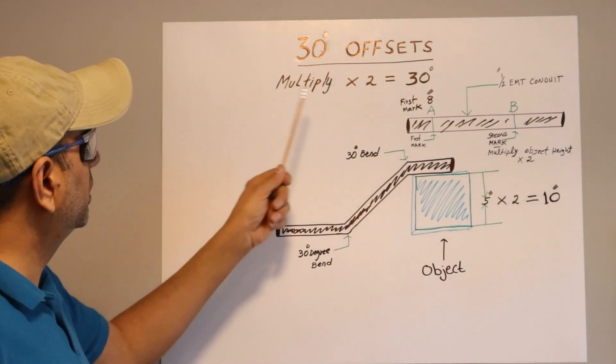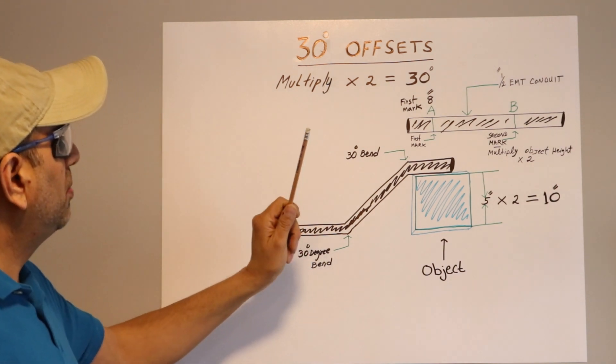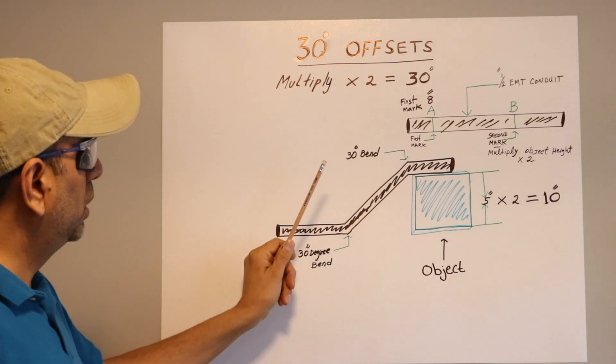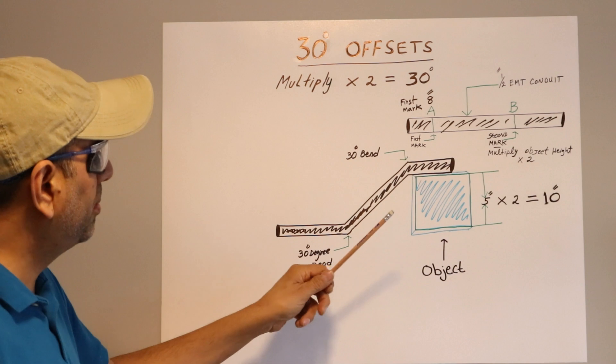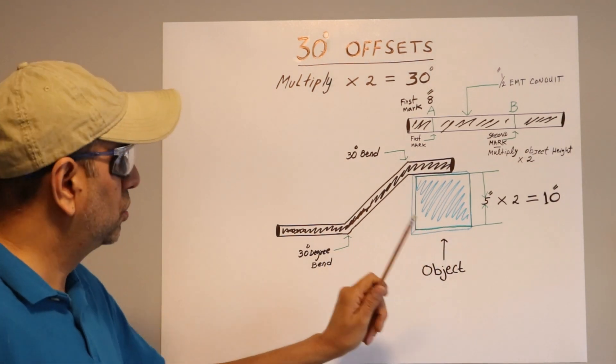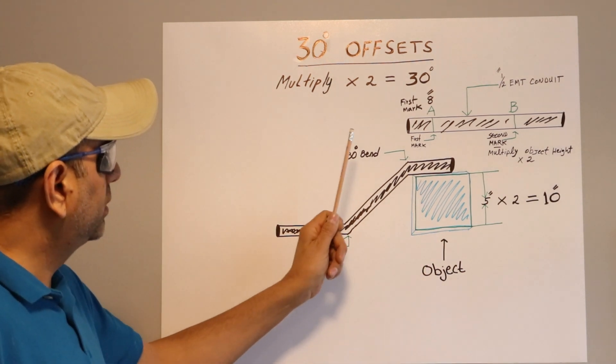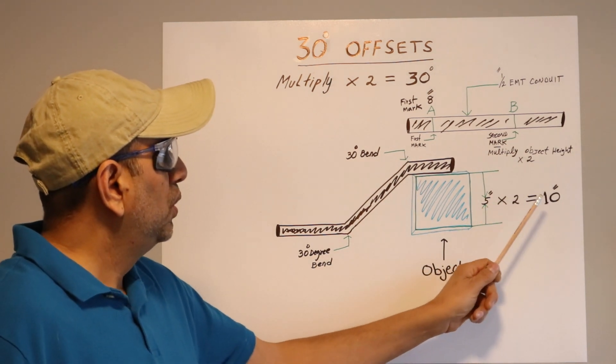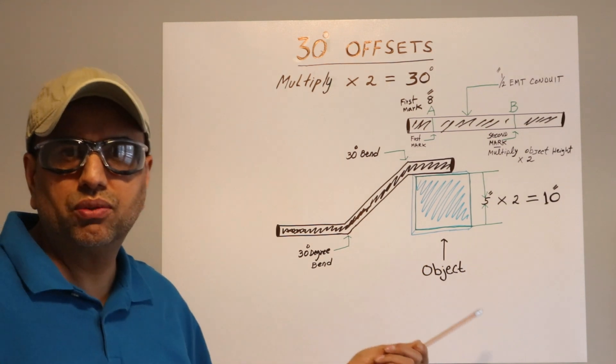You only have to multiply by two. Let's say we have an obstacle that we want to go on top and do our 30-degree bend. Let's say that obstacle height is five inches. When it's five inches, that means we're doing a 30-degree bend. Five inches multiplied by two equals ten.